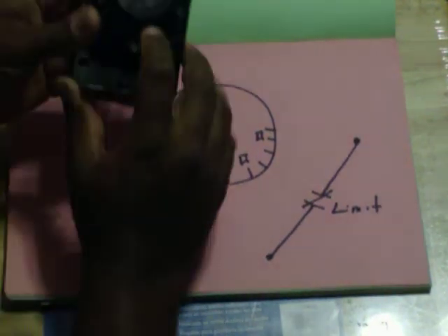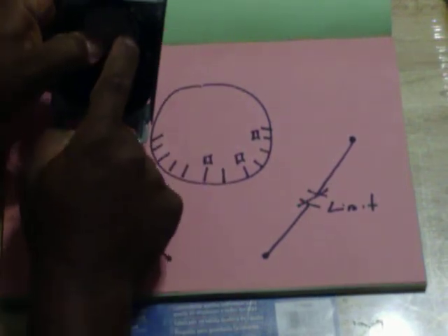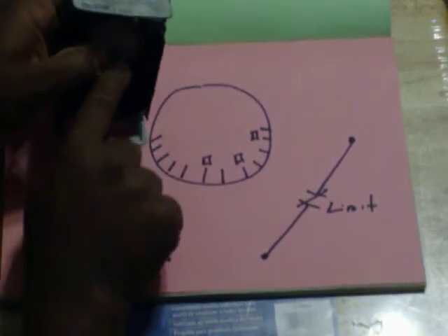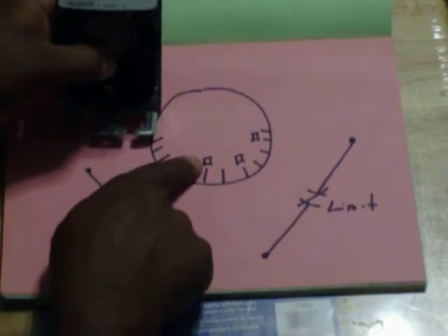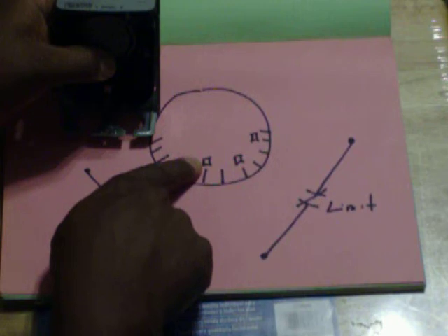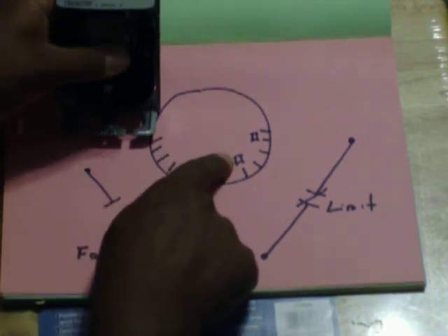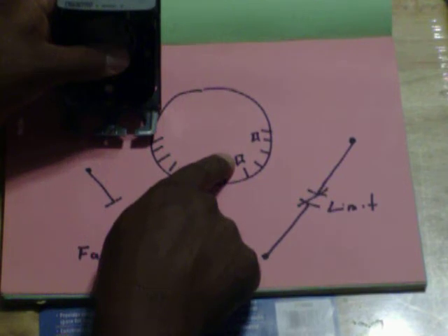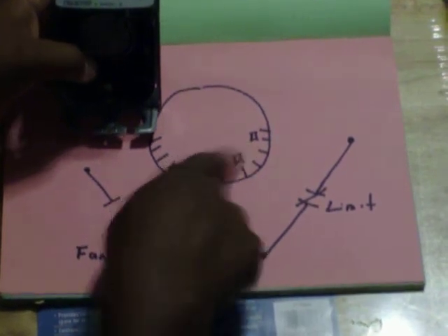First, these three little squares I've drawn here, these are actually set pins. And you need to remember these set pins. The very first set pin you come to is going to be fan off. This is the fan off. Second set pin in the middle is the fan on. Third set pin is your limit switch.